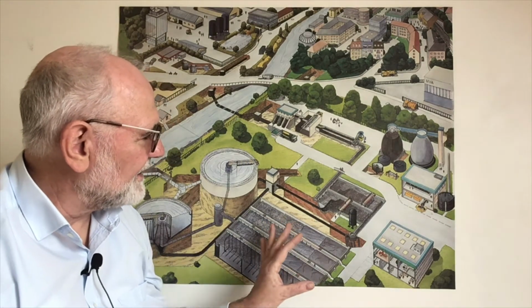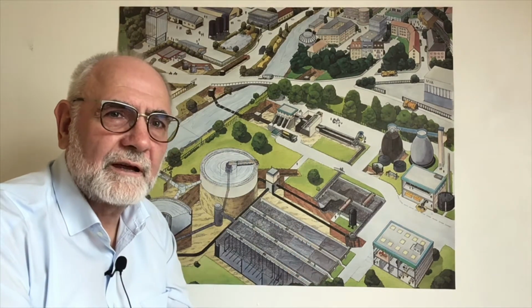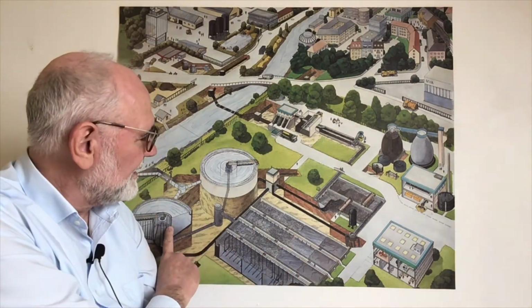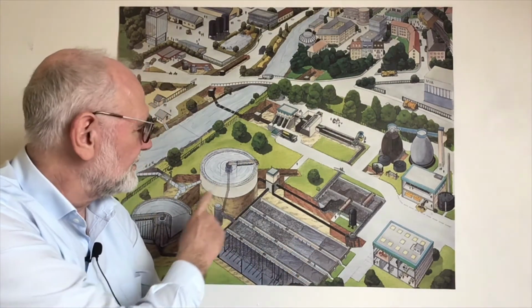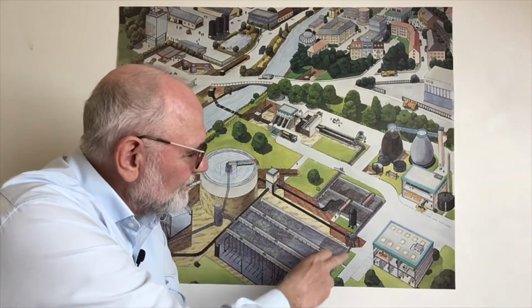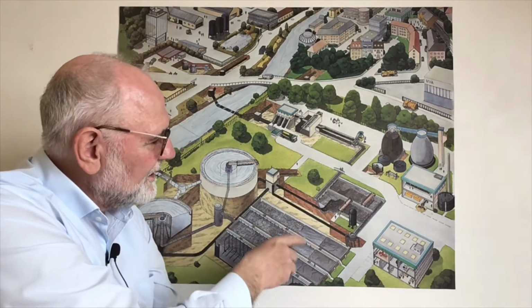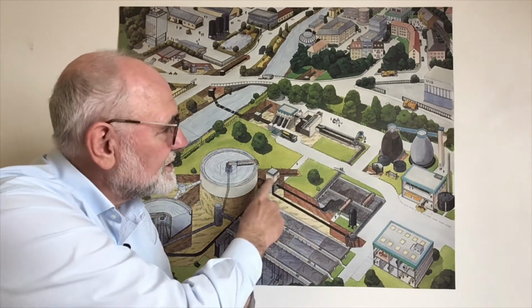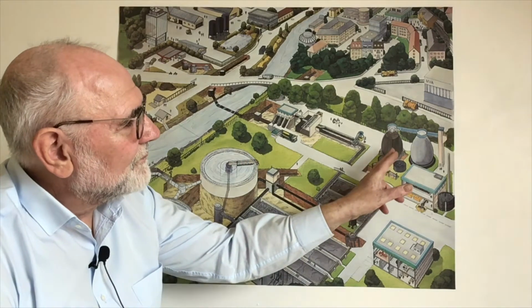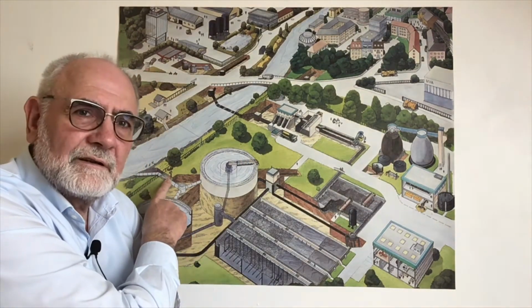Okay, that's the activated sludge process. It's more than 100 years old. It was invented in the UK, in Manchester, more than 100 years ago. Then it goes to the secondary settlement. These are round basins over here. Again, the sludge goes down here, and we pump the sludge back to the aeration area. So it runs in a circle. If you have surplus sludge, it goes again to the sludge pre-thickener over here, and then later on to the sludge area. Here we showed a measurement area.